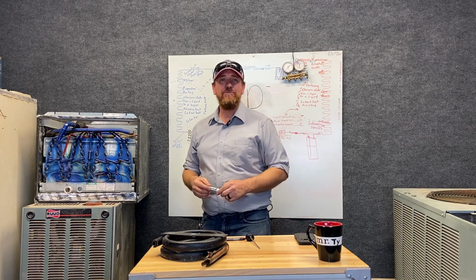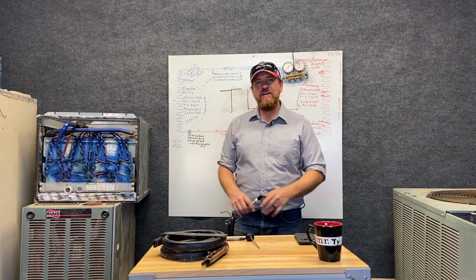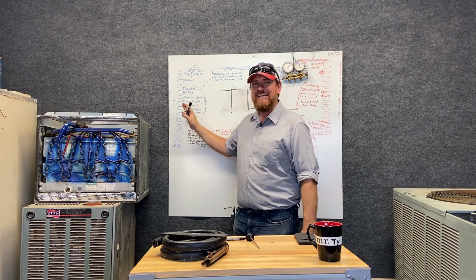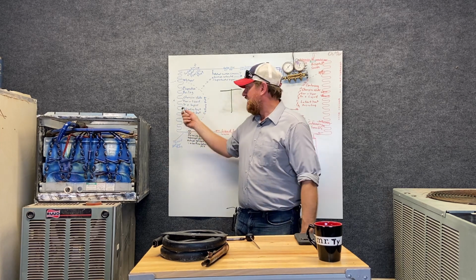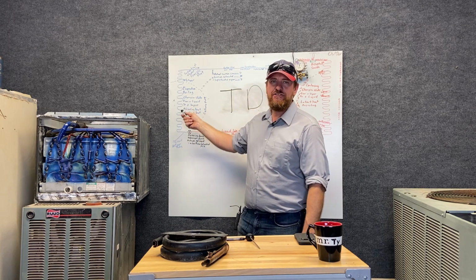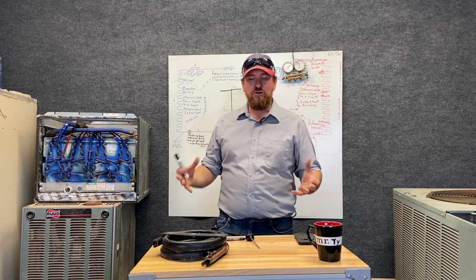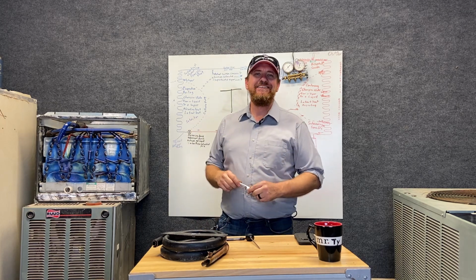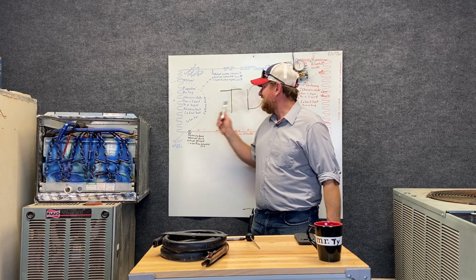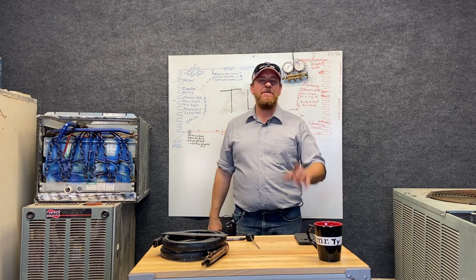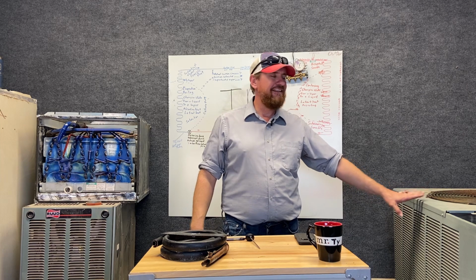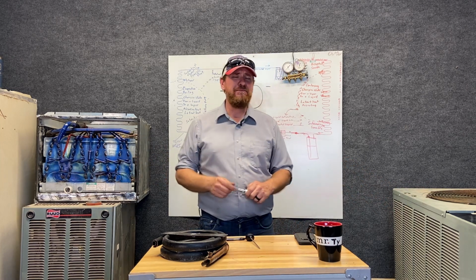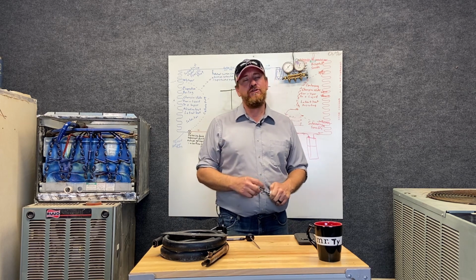You've heard of a creamery that uses a cold stone. Well, we have an evaporator under that stone, or someone's glycol, and we take the heat out of the stone. So there's going to be a temperature of the refrigerant versus a stone. And then as you're working the ice cream on it, the heat leaves the ice cream and goes to the colder or less heated stone. So about heat transfer, TD is going to be a very important number. Especially in residential, we're going to be looking at TD for the condenser, but there's also, when we get into refrigeration, TD is a very important number, especially when we're looking into walk-in coolers and walk-in freezers.